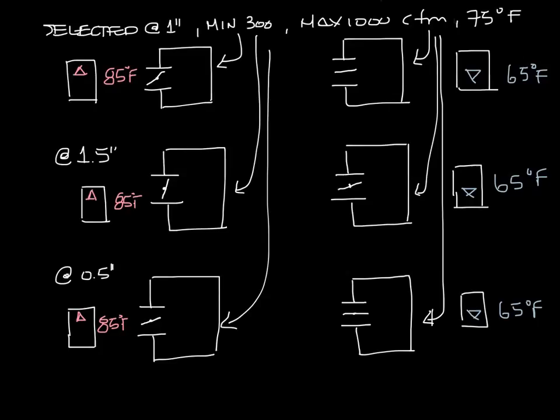This is why I said the damper should be almost open in your design condition. If you select the box so that full open is maximum CFM, you don't have any room to open the damper anymore. Or, if your inlet static pressure is lower than the pressure you selected it at, you may starve your box for air.